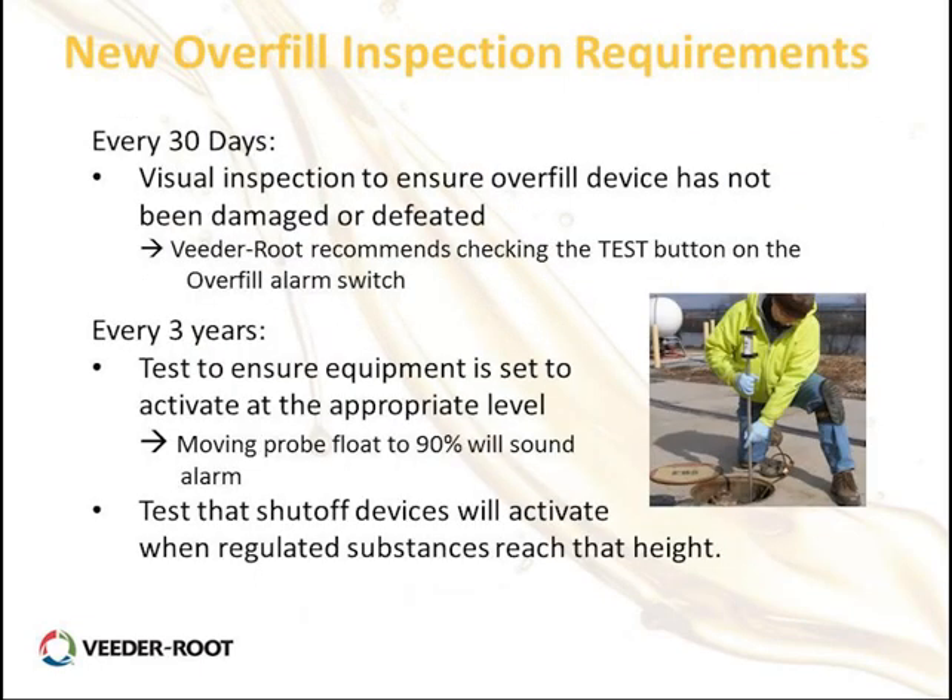Regarding overfill inspection requirements: every 30 days they require some type of visual inspection to ensure devices are not damaged or defective. Veeder-Root recommends using the test button on the overfill switch to confirm power, light, and buzzer are functioning. Every three years you must test the equipment and activate it to verify it works at the 90% level — move the probe float to simulate a delivery exceeding 90% and confirm it generates the alarm. For shutoff devices, verify it activates and prevents product from reaching 95%.